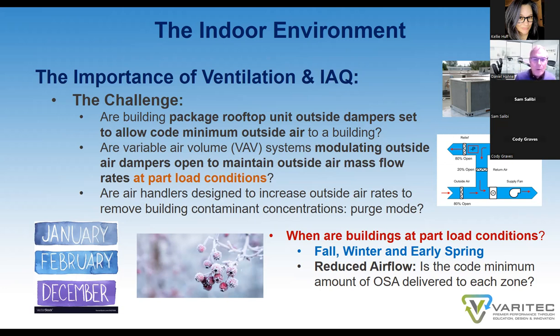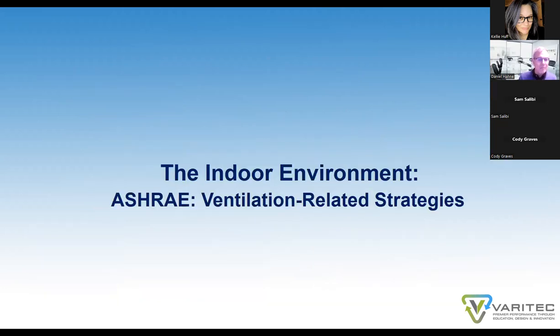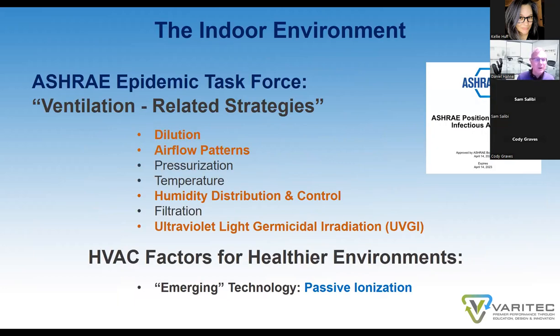Well, when are buildings at part load conditions? Fall, winter, and early spring. And that's where we need to ask ourselves whether or not our institutional buildings or larger commercial buildings that have variable air volume systems are actually providing the outside air minimum rates prescribed by ASHRAE 62.1. So let's look at various ventilation-related strategies for the indoor environment. What strategies can be applied to improve IAQ and reduce the risk of infection?